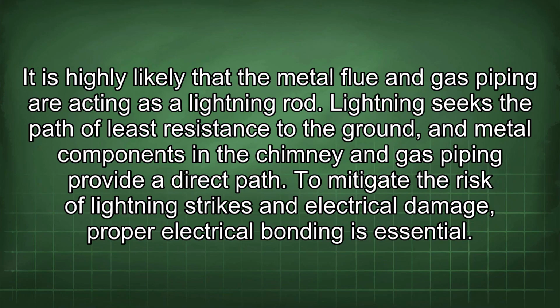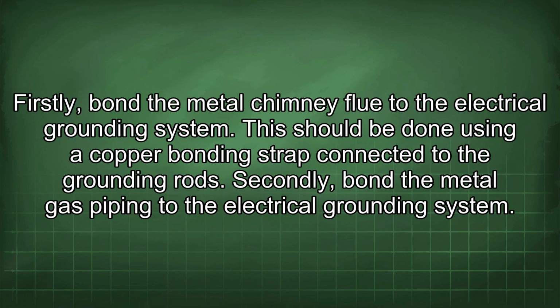It is highly likely that the metal flue and gas piping are acting as a lightning rod. Lightning seeks the path of least resistance to the ground, and metal components in the chimney and gas piping provide a direct path. To mitigate the risk of lightning strikes and electrical damage, proper electrical bonding is essential. Firstly, bond the metal chimney flue to the electrical grounding system.